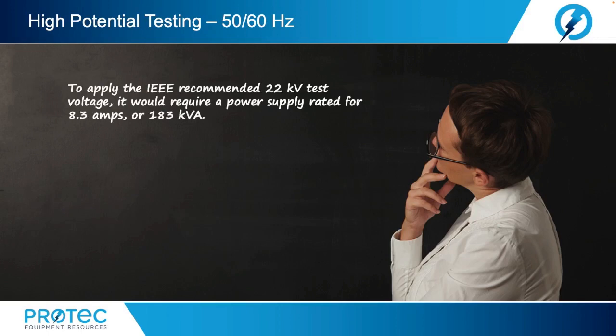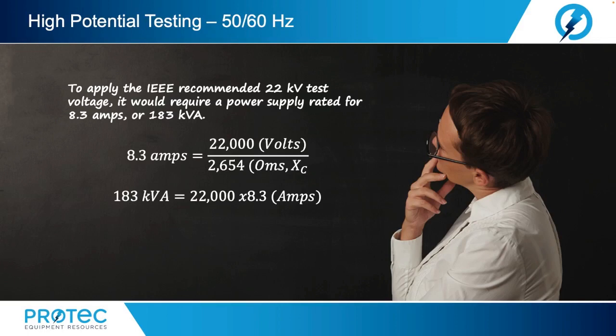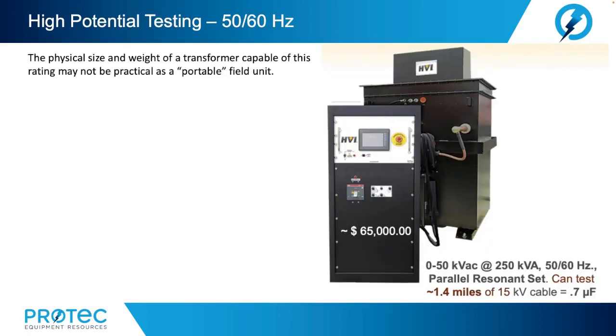Now, in order to apply the IEEE recommended 22,000 volts of test voltage, it would require a power supply rated for 8.3 amps or 183 kVA. As we see in the formula, 22,000 volts divided by 2,654 ohms would be 8.3 amps. Multiplying the 22,000 volts by our 8.3 amps, we would get our 183 kVA requirement. Now, the physical size and weight of a transformer capable of this rating may not be practical as a portable field unit.